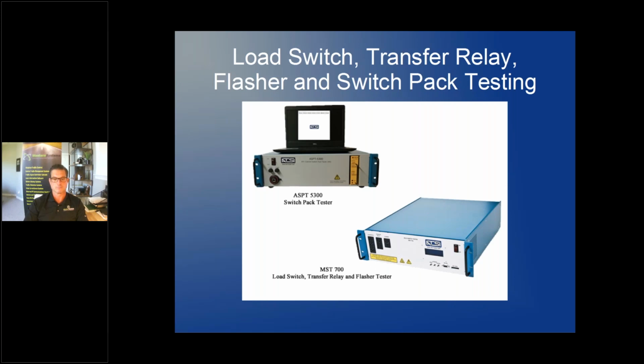This means that if you have an ATC cabinet, in order to test your monitor, you really should be testing the CMU, which would require the ACMT 5000 that I showed earlier. You should also be testing the switch packs. If you're familiar with testing, you know one of the most important parts of testing the conflict monitor is the channel voltages, making sure the lights are on or off at the proper voltages. If you're not testing the switch pack, you're not testing that in the ATC cabinet.